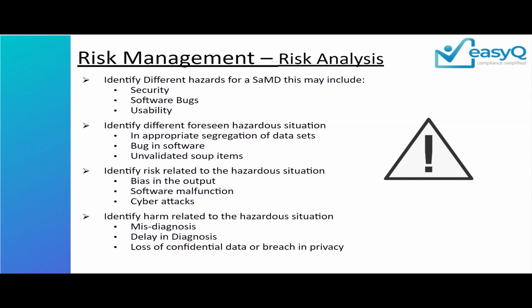It has been validated, tested, it goes through the entire round of your unit testing, integration testing, system testing, and even validation before you qualify it as part of your product, and then you release into the market. Also, for these SOUP items, ensure that you have a good configuration management system. All of this is going to help you reduce the risk related to the SOUP item. So the controls over SOUP, or the risk related to the SOUP items, is also something that you should think about when you're doing your risk analysis, primarily for any SaMD companies.